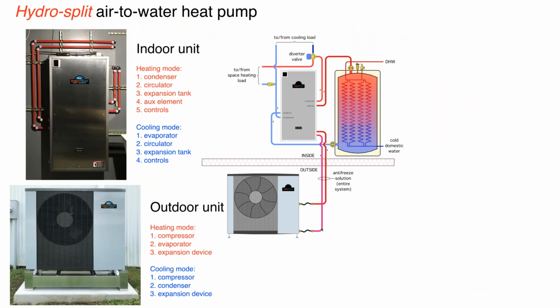Another variation is what's called a hydrosplit system. This is basically when we're taking a monoblock outdoor unit and selling it along with an indoor unit. And the indoor unit would contain many of the products that would otherwise have to be individually selected and installed. Circulators, diverter valves, controls, expansion tanks, purging valves, and so forth. The box you see in the upper left there basically is, if you will, the indoor portion of the system in a box. And the piping is really reduced down to running 2 pipes out to your heating or cooling terminal system. You're running 2 pipes out to the heat pump. And in this case, you're running 2 more pipes to an indirect water heater. So manufacturers that provide this are trying to simplify and speed up the in-field, or on-site, work necessary to install one of these systems.